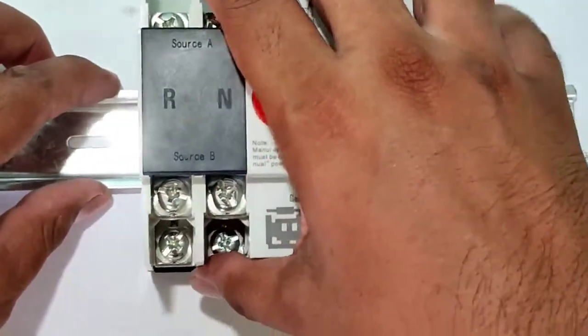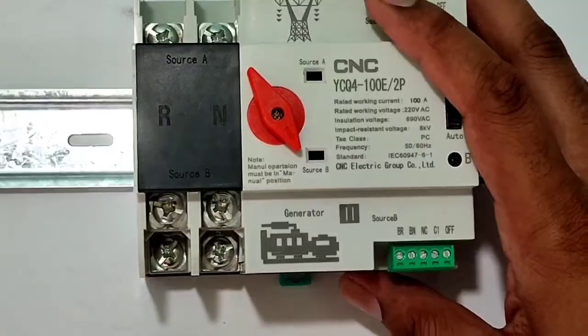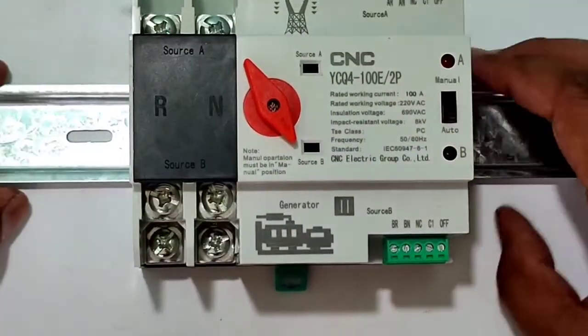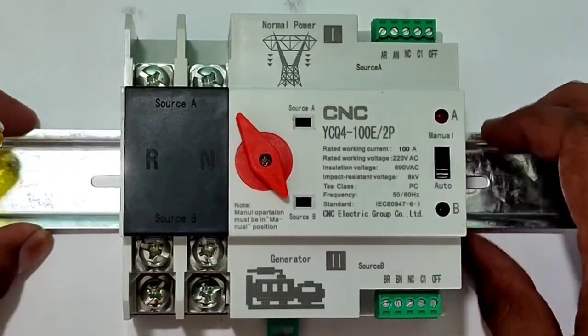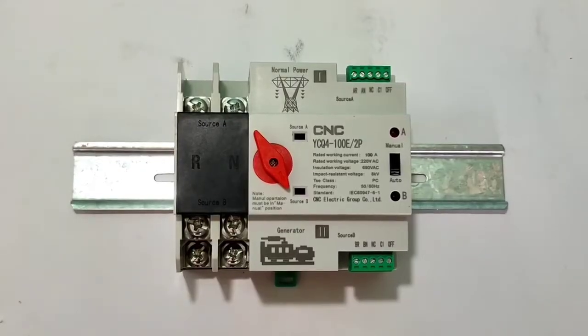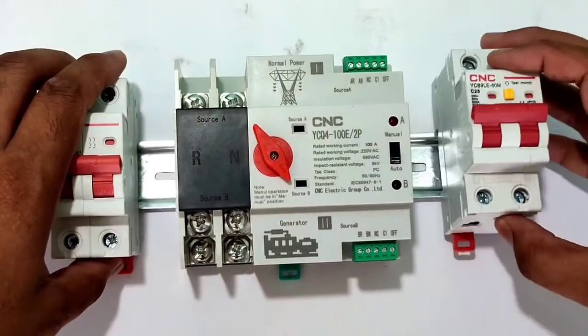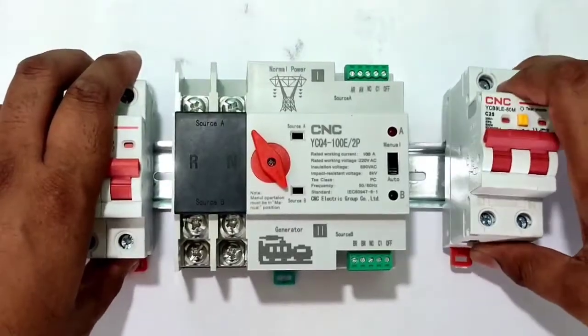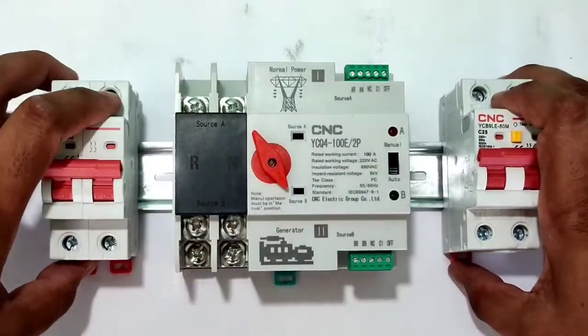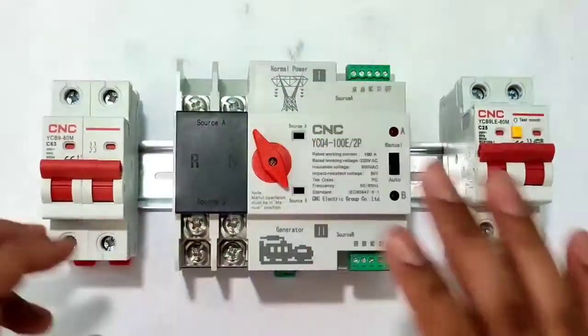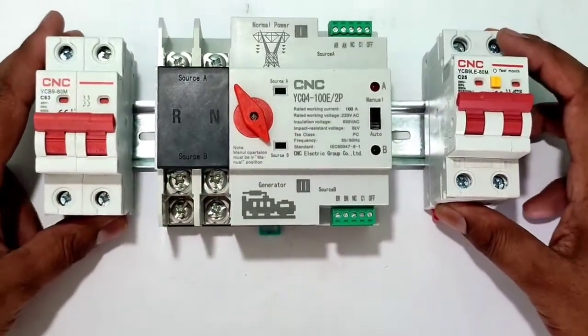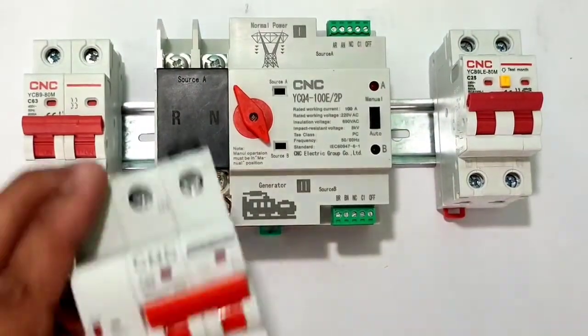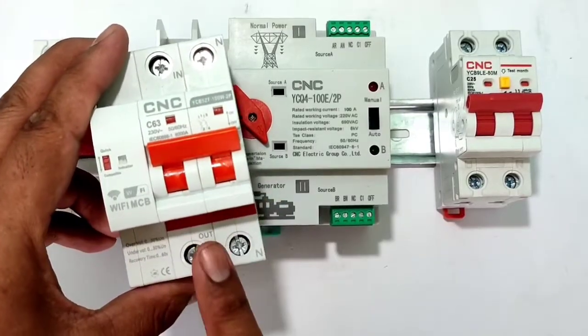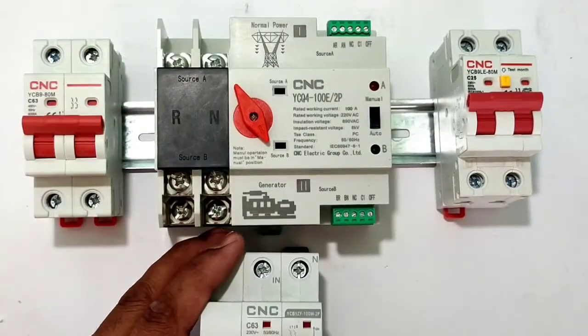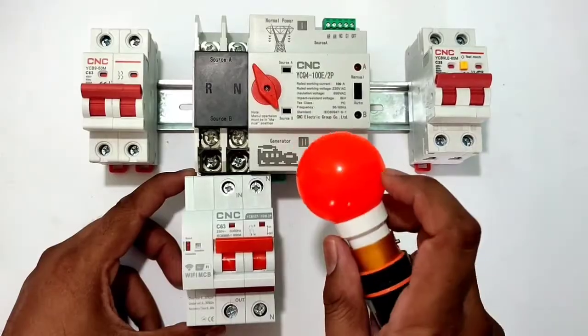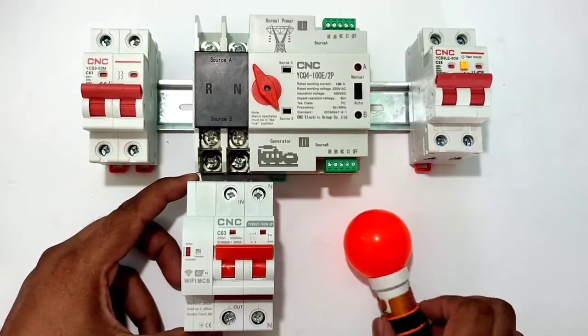First, connect this automatic transfer switch to this DIN rail. Okay, we connect here. Now, for the main power supply, we connect one circuit breaker here. You can see here, for main power supply. And a second circuit breaker for generator power supply or inverter power supply. Okay, so we connect two circuit breakers. Also, we connect one more circuit breaker for controlling the load. So for load control, we connect one circuit breaker here. And as a load we connect one bulb, as you know. Now let's see the input connection.